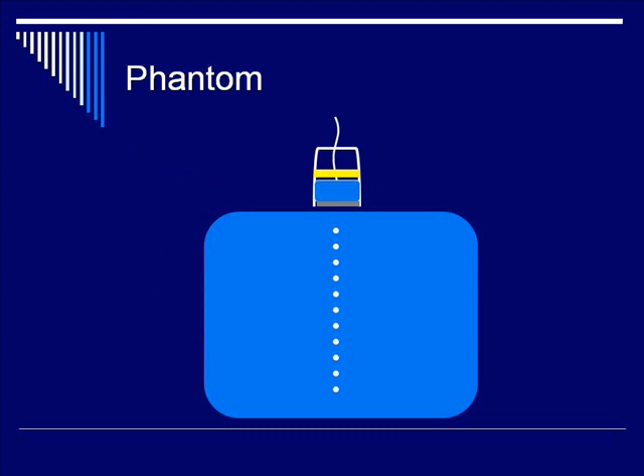When you've seen these phantoms underneath the probe, you've noticed that they're not just homogenous tissue underneath — they usually have reflectors within them. Sometimes these reflectors are hyperechoic targets; sometimes they're liquid-filled tubes to resemble anechoic structures. Here we have a mock drawing of a tissue-mimicking phantom that we may refer back to as we discuss specific ultrasonographic properties.